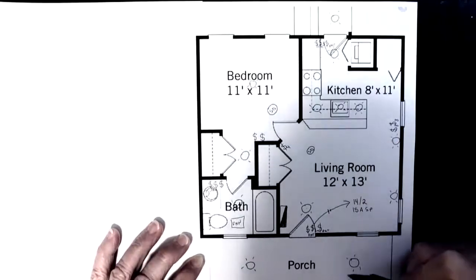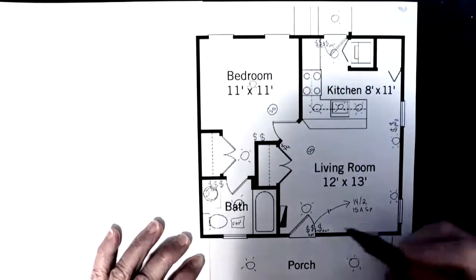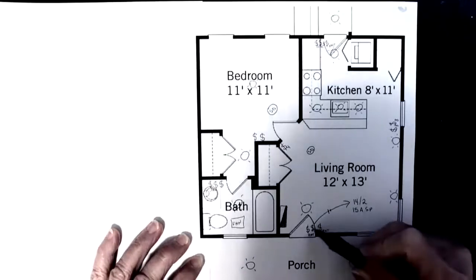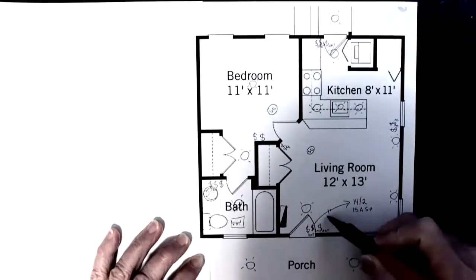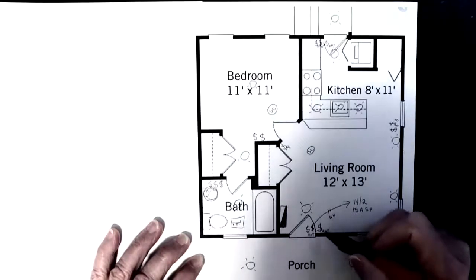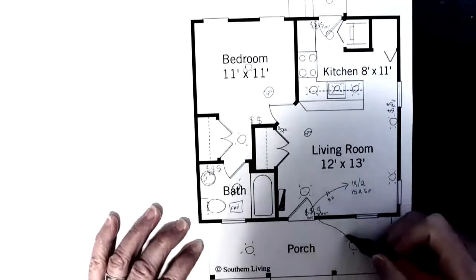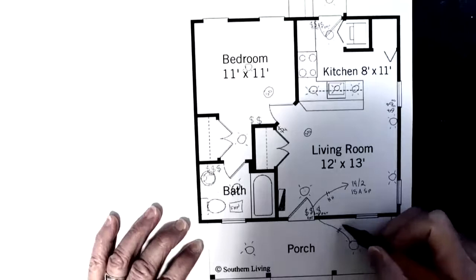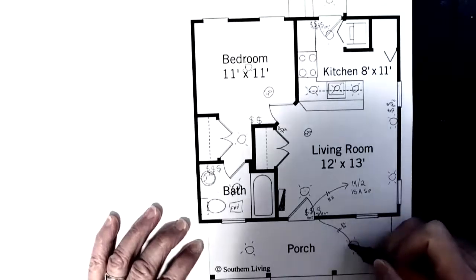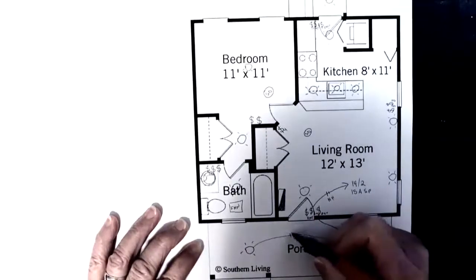As I mentioned in the previous video, we laid out these lighting here in each area, and where the switches are going to be. So, at the front door here, I've taken power, which is a hot and a neutral, to that set of switches. And that means then I can pick up my porch lighting and go from the outside light switch, take a switch leg and a neutral up to that light, and then I can go over and pick up that one as well.